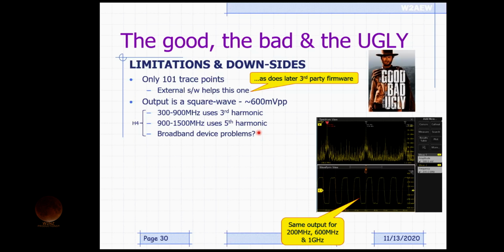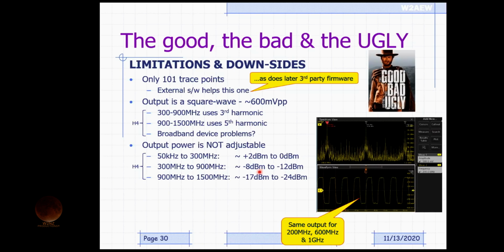If you're measuring a broadband RF amplifier, for example, you've got to think about the fact that you're supplying it with a signal that is rich in harmonics, and it's not just a pure RF signal. And is that going to pose a problem? Okay. The other problem compared to a true VNA is that the output power is not adjustable. Okay, it's a square wave of essentially a constant amplitude.